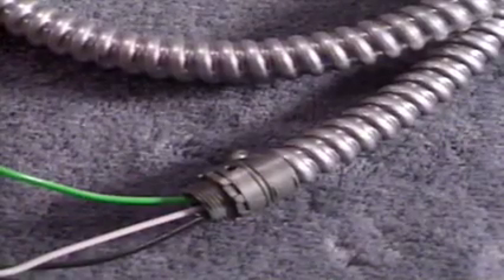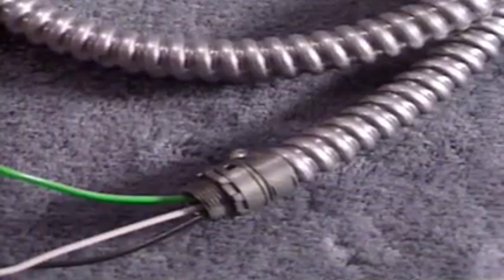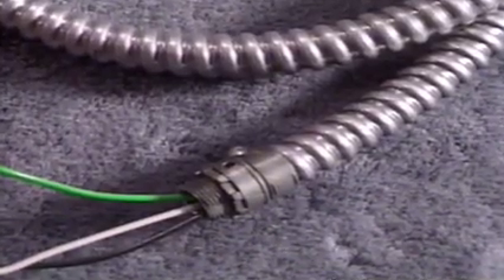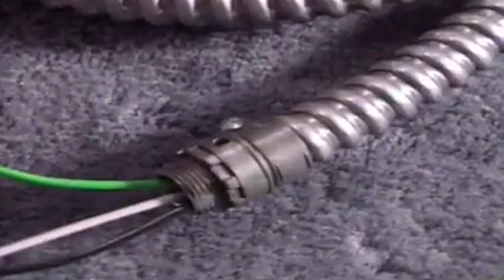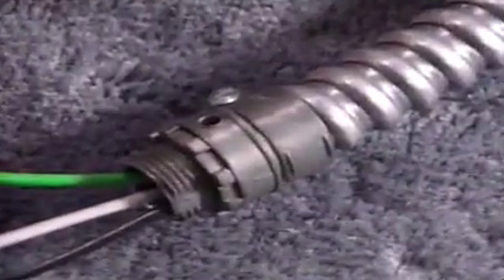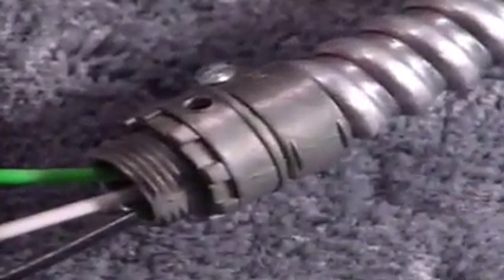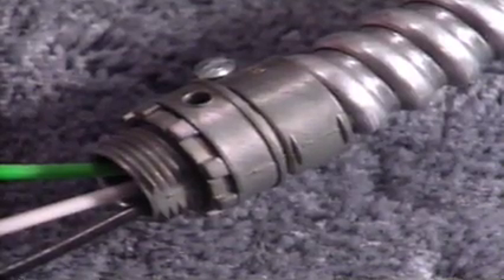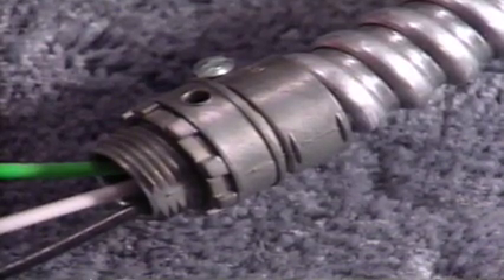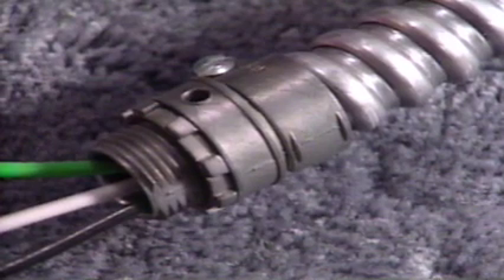Flexible armored cable is sometimes called BX cable. This is insulated wire with a flexible metal covering. During installation, anti-short bushings are inserted at the end of BX cable to prevent the cutting of the wire insulation by the sharp metal armor.